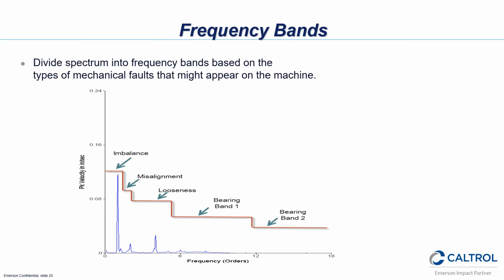So, frequency bands. When we're measuring, this is a typical spectrum. What I was talking about is where we set up bands with every set of data that we collect. And again, you may be using some vibration pens out there where you're getting a number that you can trend, and it has value too. But it takes all these frequencies that we're seeing within a spectrum. Each one of these frequencies represents something on the machine.